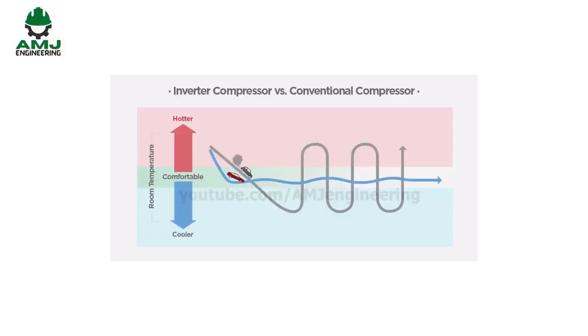The following illustration shows the difference between a conventional HVAC compressor that runs at maximum operation load until the desired temperature is reached and turns off until cooling is required to reach the set temperature again. So, the compressor is continuously turned on and off. On the other hand, an inverter compressor will continue to run, but only use the required amount of energy to maintain the desired temperature. This variable speed operation is not only more efficient, but also maintains more precise temperatures. In addition, this continuous smooth operation of the compressor translates to fewer maintenance calls and a longer lifespan for the motor itself.